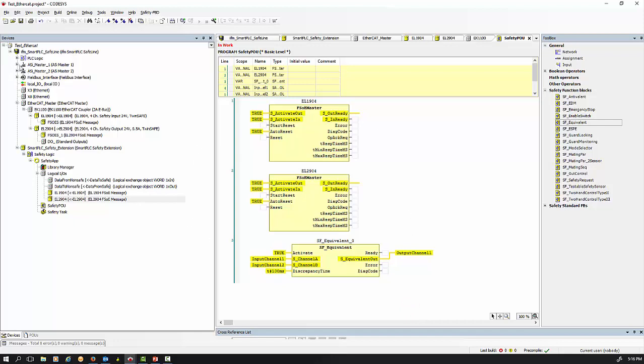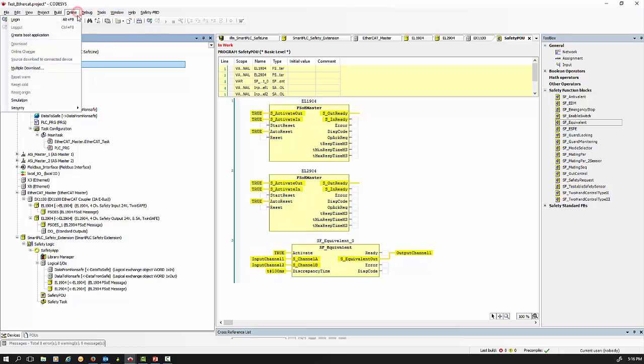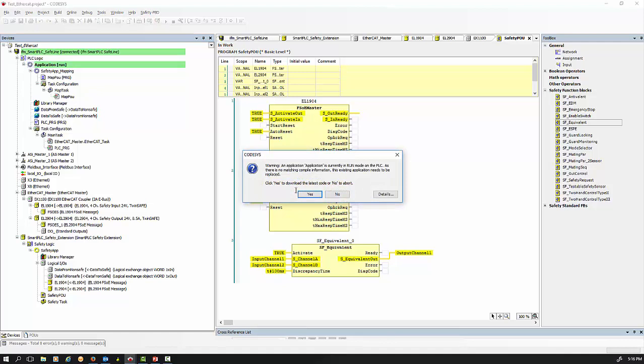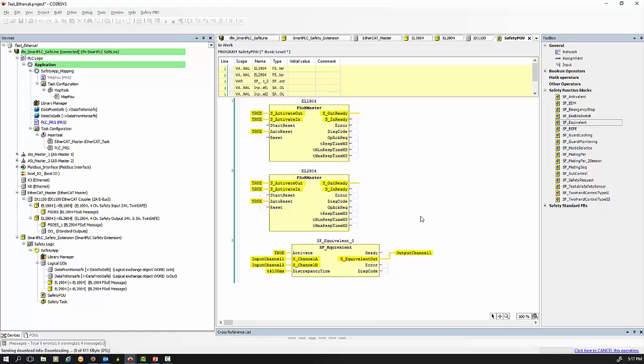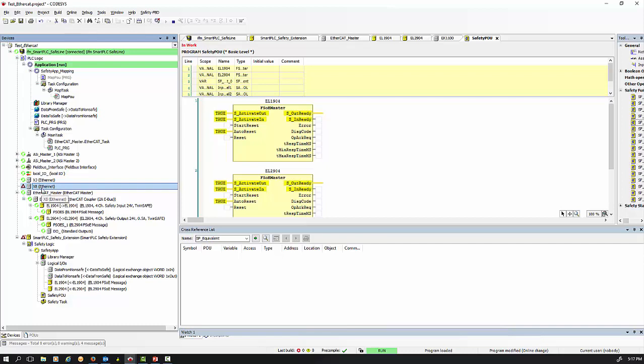The application is shown as bolded, meaning the login and download buttons apply to it. Download the non-safe PLC first to make sure all non-safe IOs like EtherCAT get established and running, which makes your life a lot easier. After the download, start the PLC. Don't worry about port X8 not being active — this is an older hardware version without a port X8, but the software is updated and it won't cause problems. Make sure EtherCAT is running and all modules are running.